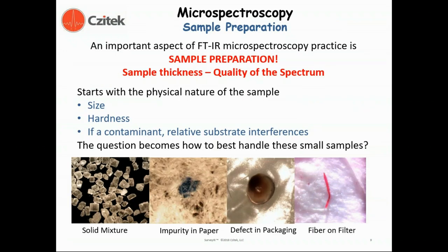Microspectroscopy sample preparation is one of the most important aspects of microspectroscopy practice. The quality of the spectrum you get from an FTIR microspectroscopy system is very much dependent on the preparation of the sample. One of the more important issues in sample preparation is sample thickness — it is a common issue that samples can be optically thick, bands can be totally absorbing, and therefore your ability to determine chemical composition is limited. We want to ensure that samples are presented at an appropriate thickness.